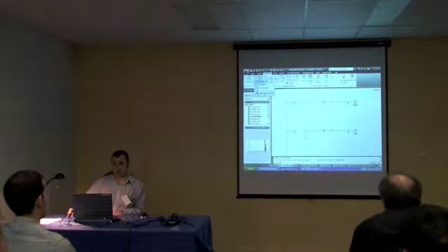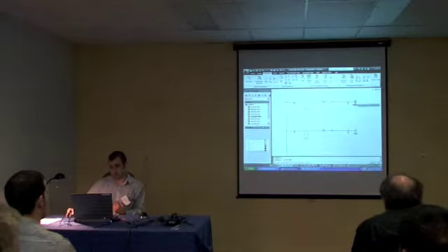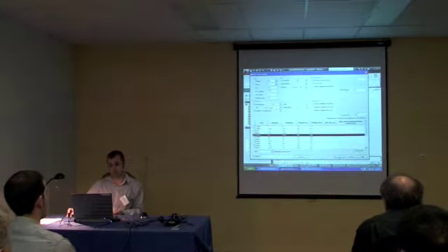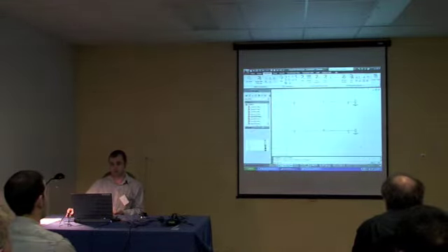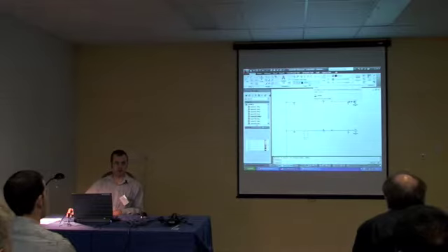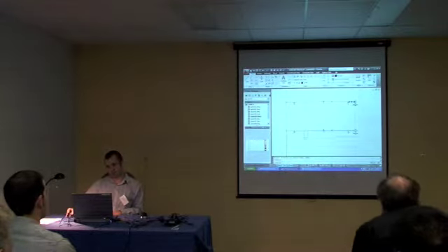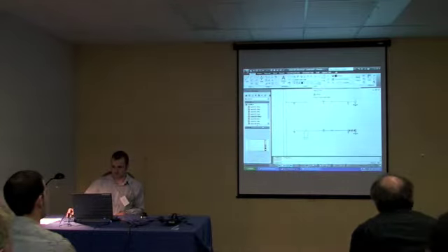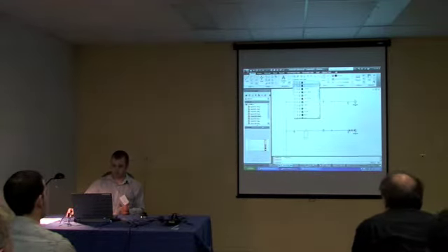Inside the circuit builder there's a recalculate wire size. So you can go back and say, well, I want to recalculate for this motor the wire size, and it puts me back where I was before and say, right, I want 10 square mil. And it goes and changes it. So now, on my layout, I've got a 10 square millimetre wire running to this motor, as opposed to the 1.5, which would have been this guy.